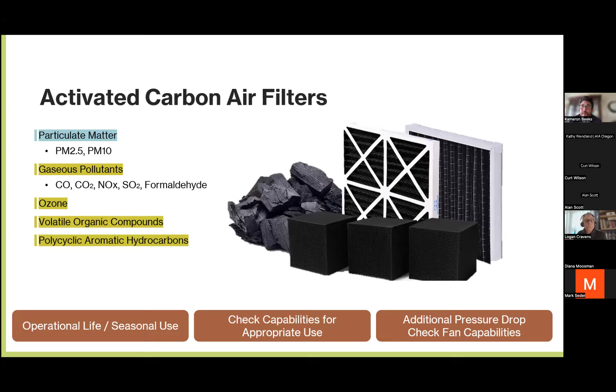So the other thing is that you have to make sure that they're appropriate for the type of use that you're deploying them for. Not every carbon air filter is the same, and so just make sure you're working with your mechanical engineer or with your vendor for your filters to ensure you're getting the appropriate carbon air filters. And then I'll talk about it in a little bit more detail, but there is additional pressure drop associated with these filters. And so we'll have to make sure we check the fan's capabilities. One important note is that carbon air filters do not replace particulate matter filters. You need both. They need to work in tandem with each other. You cannot have just a carbon air filter without a particulate matter filter.